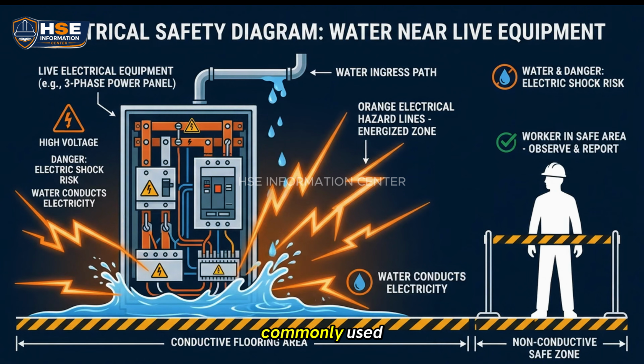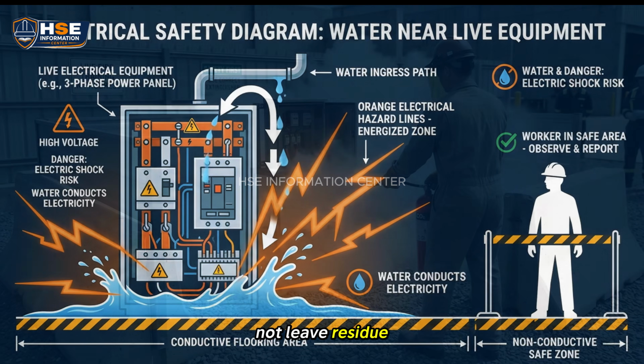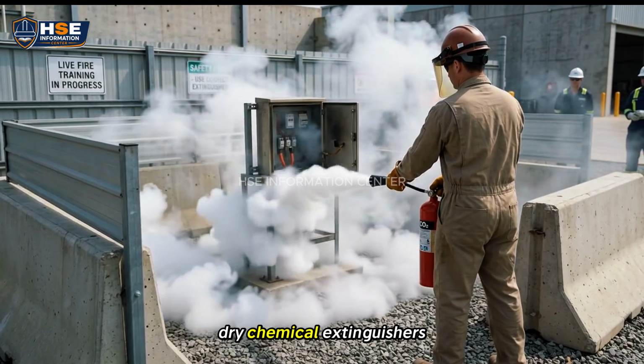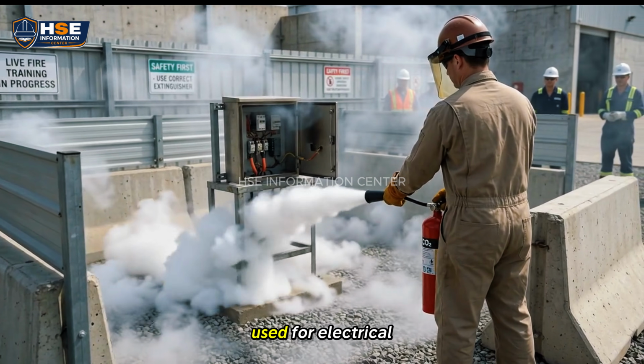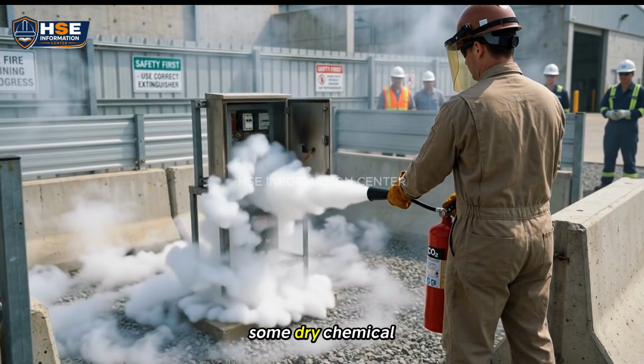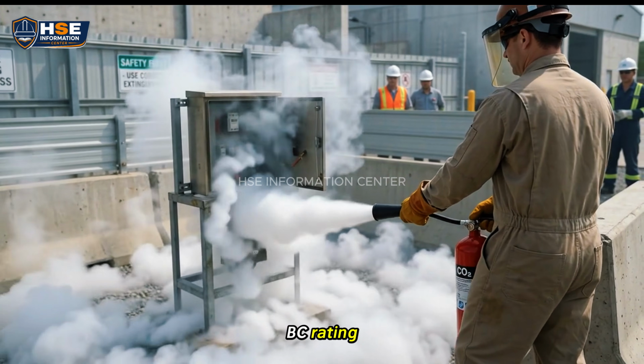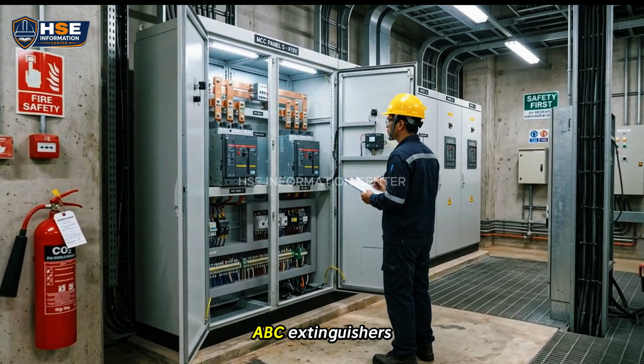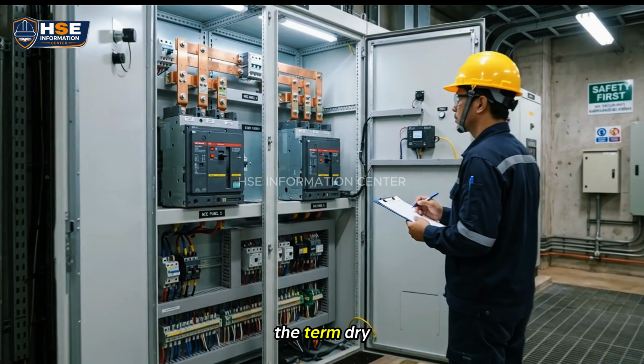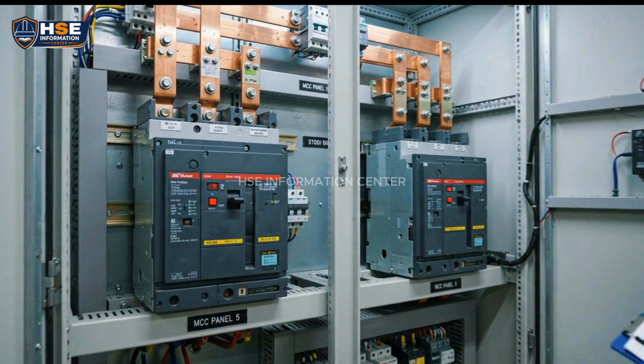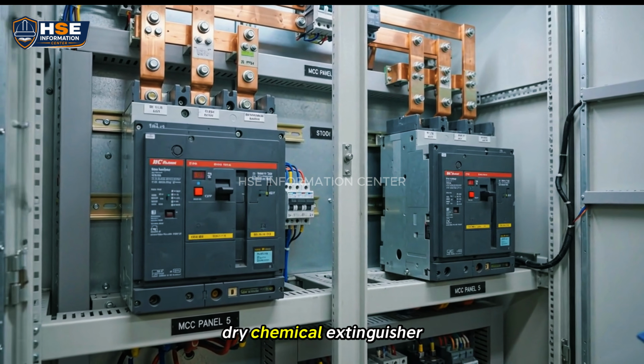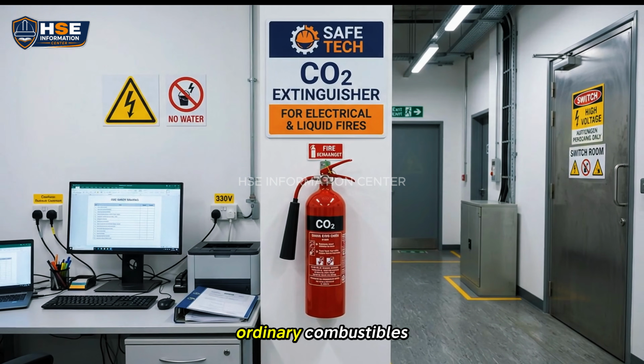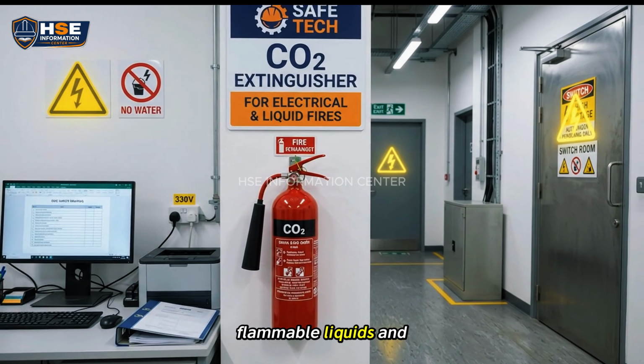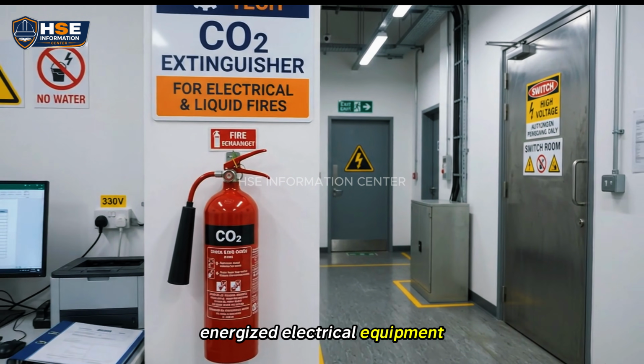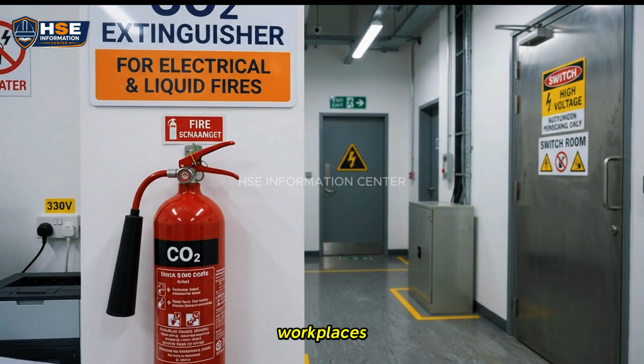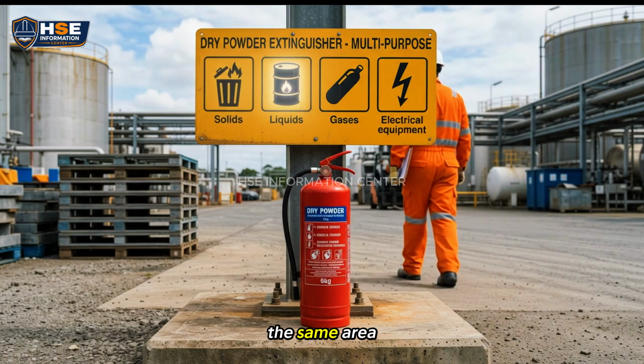CO2 extinguishers are commonly used because they do not leave residue on electrical equipment. Dry chemical extinguishers are also widely used for electrical hazards. Some dry chemical extinguishers carry a BC rating. Others are multi-purpose ABC extinguishers. The term dry chemical is important. A multi-purpose ABC dry chemical extinguisher can protect against ordinary combustibles, flammable liquids, and energized electrical equipment. This makes it common in many workplaces where several fire hazards exist in the same area.